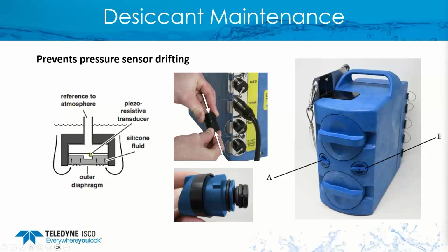So this is the pressure transducer that's in the area velocity sensor. It's a piezo-resistive transducer, and it has a referenced atmosphere. And so normally what happens when it has referenced atmosphere, the pressure transducer just changes the level reading based on the static or the head pressure over the top of the sensor. If the reference line is blocked and no longer has referenced atmosphere, as the barometric pressure increases and decreases, it will actually contract or expand that diaphragm, causing your level to change.